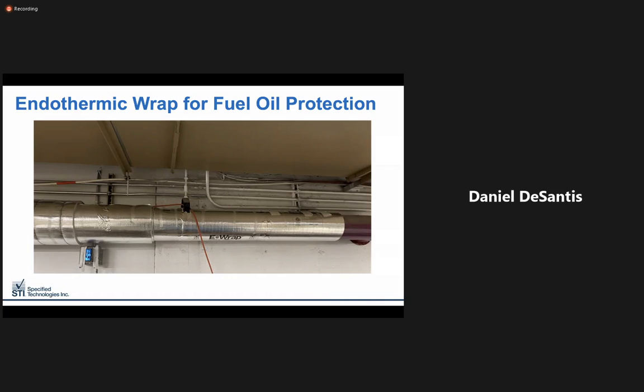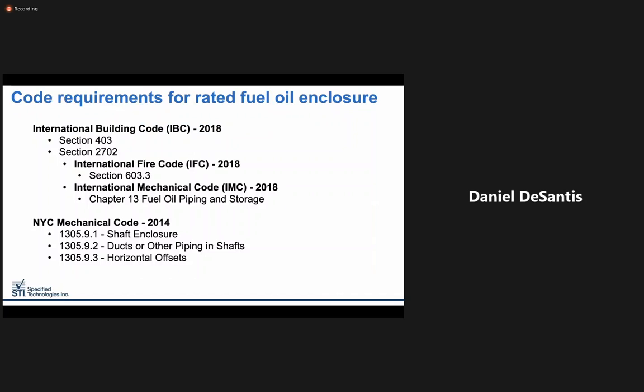Let's take a look now at the code requirements for fuel oil and how it should be protected. In the IBC, Section 403 of the code requires that fuel oil lines supplying a generator set inside of the building shall be separate from areas of the building other than the room that the generator is located in. IBC Section 2702 reads as follows. Fuel oil lines supplying a generator set inside of a high-rise building shall be separated from the areas of the building via an assembly with a fire resistance rating of not less than 2 hours.